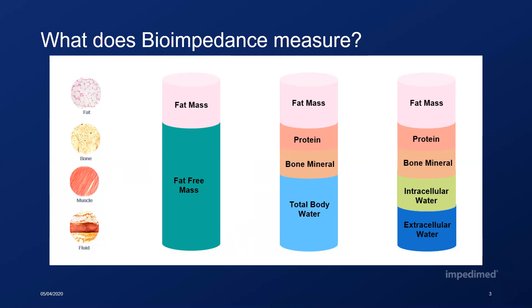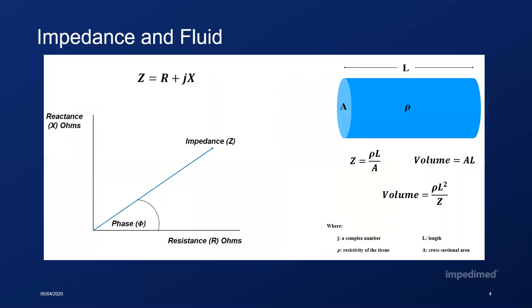Therefore the resulting impedance measured will be dominated by the fluid component of the tissue. The fluids comprise extra and intracellular fluid components. By measuring the impedance we are measuring an indicator of the fluid levels, because the current flows primarily through components with the lowest resistivity. If the amount of fluid present increases, the impedance measured decreases — they are inversely correlated because there is less opposition to current flow in the increased fluid. A change in the impedance reflects a change in the fluid levels.